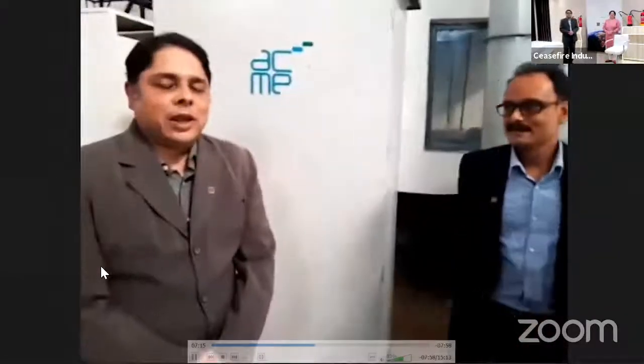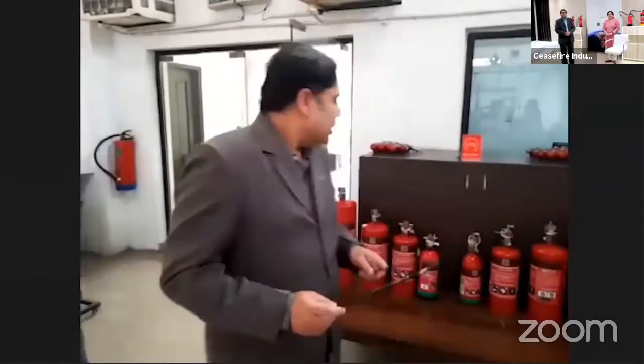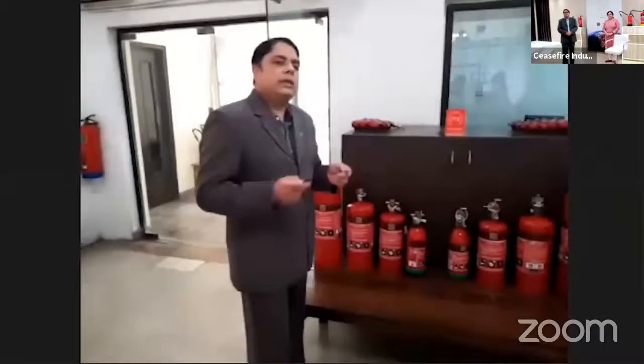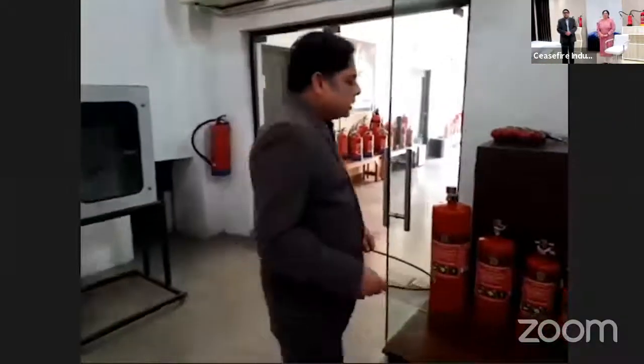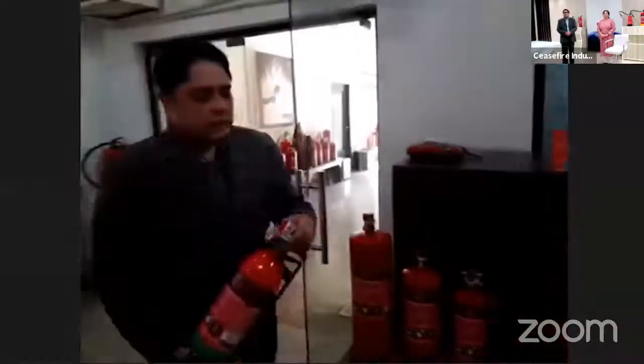Hello viewers, my name is Pranath Devan. Today we're going to give you a very brief insight into this flagship technology from Ceasefire, CQRS, the Ceasefire Quick Response System, which has a key component called the heat sensing tube. This heat sensing tube is a modified polyamide, and it flows through the system, senses the flame and extinguishes the fire. The way the heat sensing tube is connected and used in the system dictates how we categorize the system. So we have two categories, the direct and the indirect systems. For the direct system, the heat sensing tube is connected to the valve.